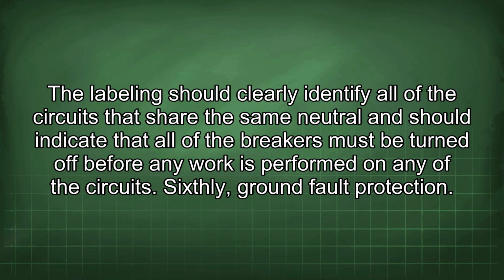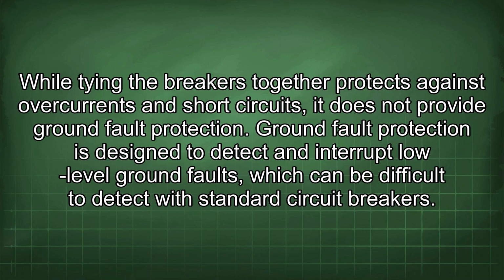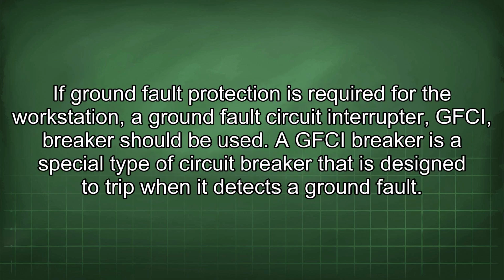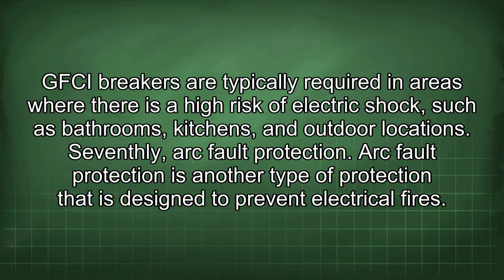Sixthly, ground fault protection. While tying the breakers together protects against overcurrents and short circuits, it does not provide ground fault protection. Ground fault protection is designed to detect and interrupt low-level ground faults, which can be difficult to detect with standard circuit breakers. If ground fault protection is required for the workstation, a ground fault circuit interrupter (GFCI) breaker should be used. A GFCI breaker is a special type of circuit breaker that is designed to trip when it detects a ground fault. GFCI breakers are typically required in areas where there is a high risk of electric shock, such as bathrooms, kitchens, and outdoor locations.